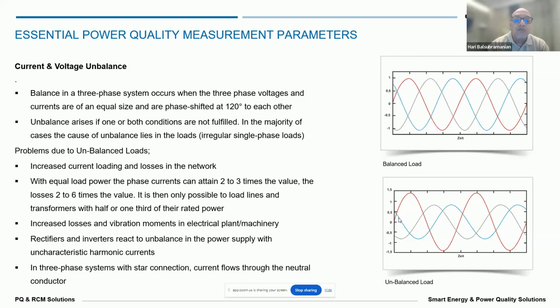So when the current is not equal, yesterday someone was asking me, I have a motor consuming 300 ampere in one phase, 250 in another, and 225 in the third phase. This is a clear unbalance, and we have to ask them to do some more inspection on the motor to check why it is consuming differently. It was a star delta starter.